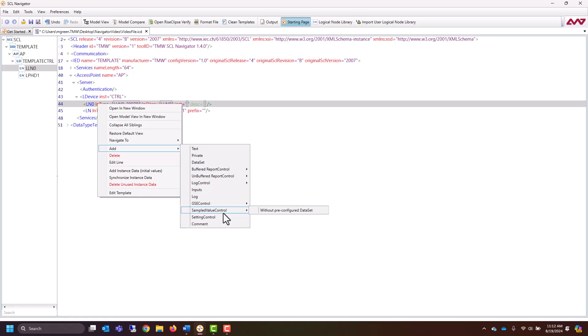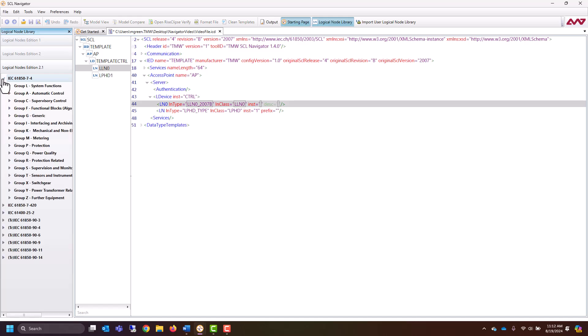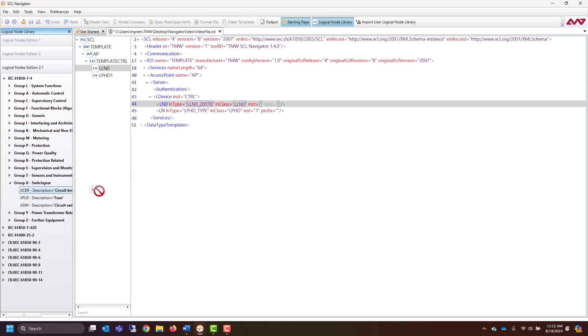We can also add new logical nodes by going to the logical node library and interacting with it. For instance, if I wanted to open up the 61850-7-4 and go down to the switchgear, I could grab an XCBR and drag that onto the template.